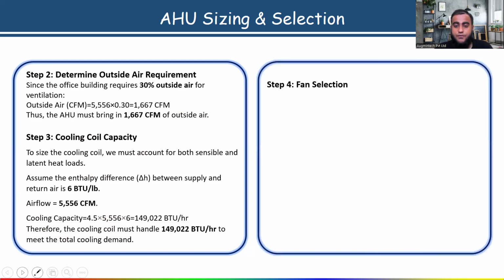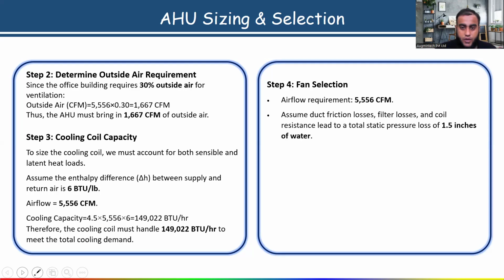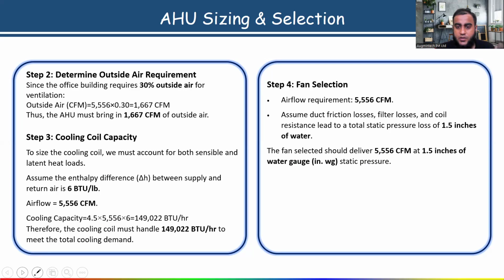Now, next thing, step 4, fan selection. Suppose the airflow requirement we have calculated is 5,556 CFM. For that, you have to assume duct losses, because we have to consider the external static pressure. Let's say we assume duct friction loss, filter losses, and coil resistance lead to a total static pressure loss of 1.5 inch of water in our case. So the fan selected should deliver 5,556 CFM at 1.5 inches of water gauge static pressure.